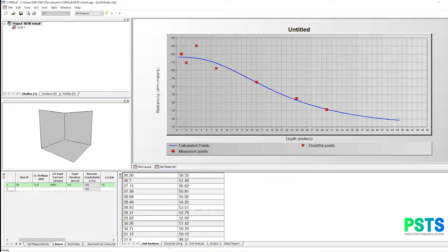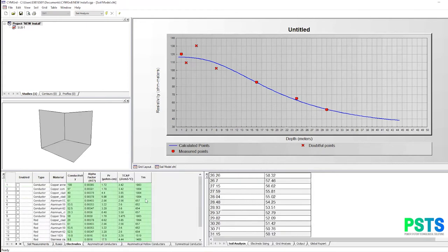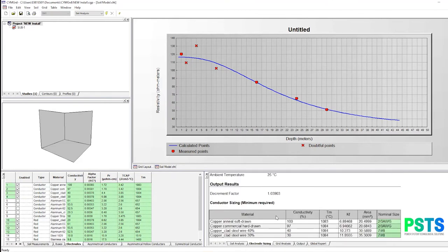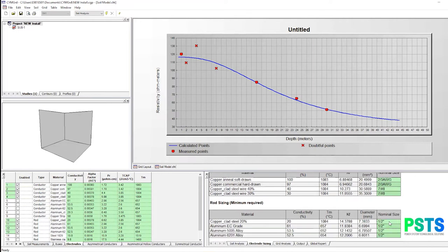So once we have that, we need to do the electrodes. Suppose you go to the electrodes and you select maybe conductors. These four conductors and these four rods. These are in the database, right? The program will automatically compute for you the minimum size of conductor required.